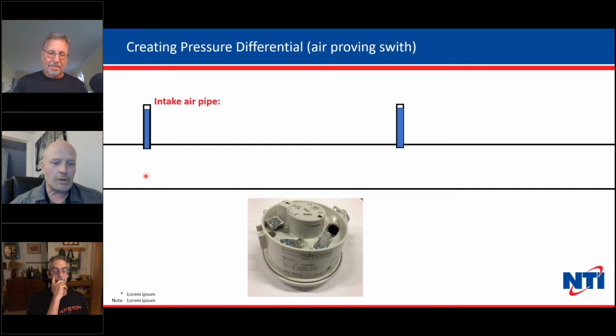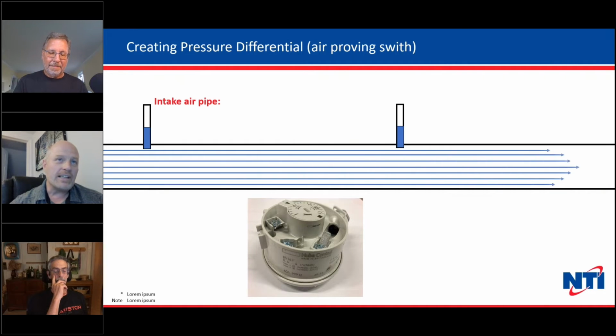So what's going to happen is at some point your blower is going to kick on, and when it does that, it's going to drop the pressure in the intake pipe, and both pressure tappings are going to see a decrease in pressure. Just like water flowing through a pipe where you get head loss and friction loss, the pitot tube, or the tube that's downstream of the flow, should see a little bit more pressure loss than the tube that's upstream. But if you've worked with any of our products, you'll notice that these two tubes are literally 6 inches apart, or not. Sometimes they're only 2 inches apart. And so the pressure difference between those would effectively be 0. It would be a very, very tiny amount of pressure difference.